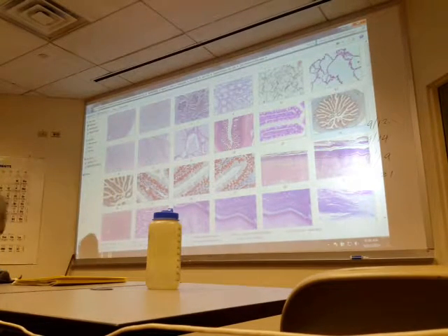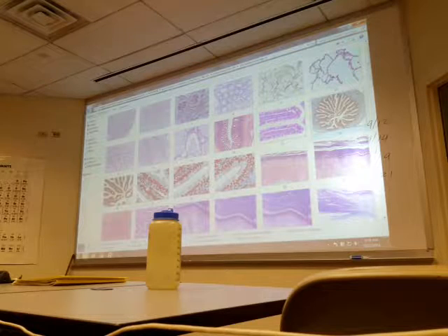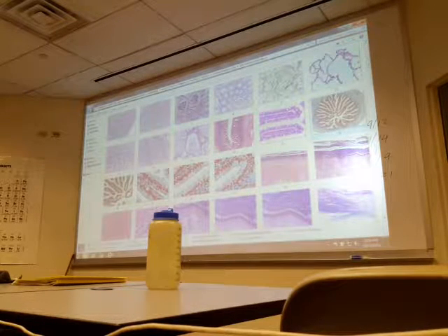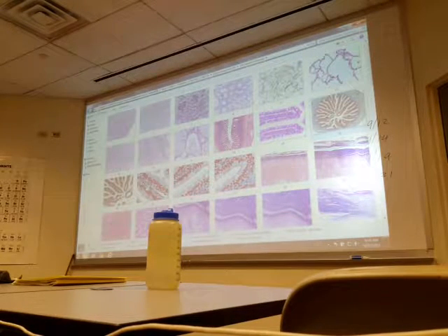But if we put one in this room, it would have to be on a foundation that wasn't connected to the rest of the building. Imagine that you're looking through a microscope right now and what you're looking at is magnified 500 times. What happens if somebody puts their hands down on the table? The vibration is magnified 500 times.